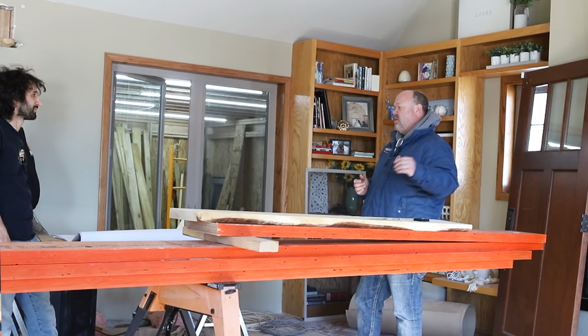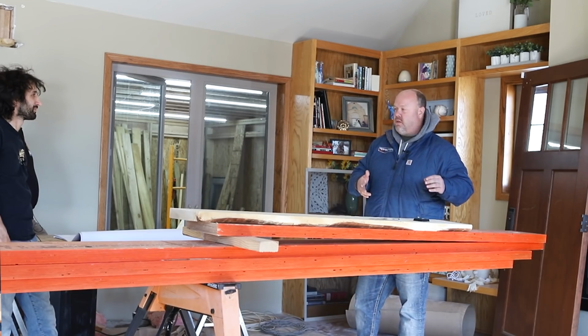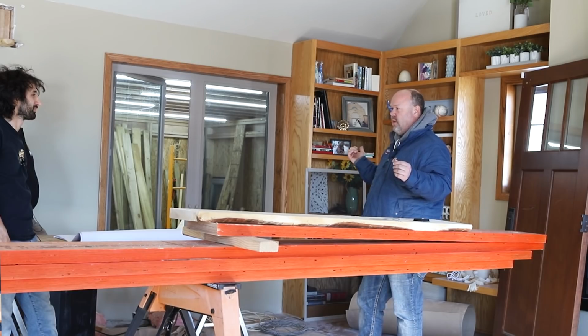And it would have affected the existing room over here, because by the time the ductwork gets out here, I'm not going to have that velocity, I'm not going to have the volume. So you can't just put an addition on, not touch the trunk line, and just add a couple extra runs.